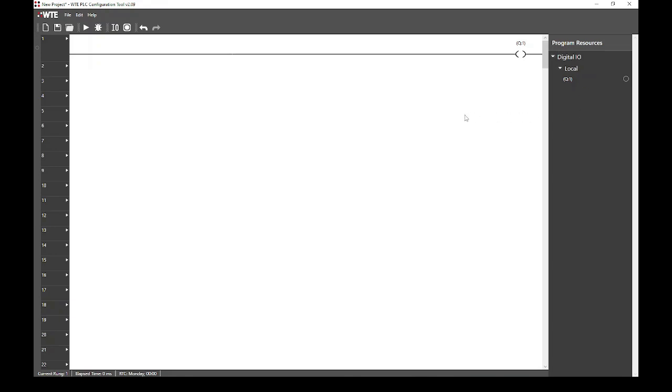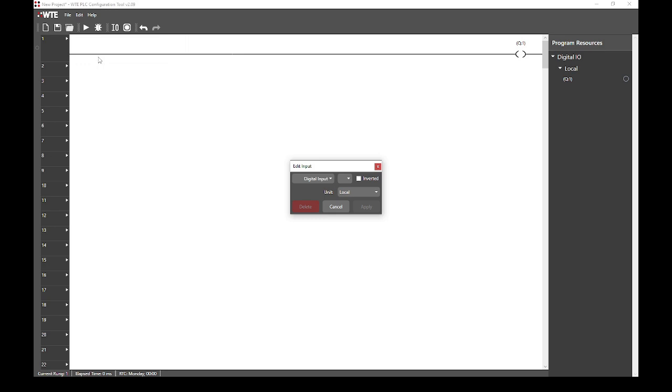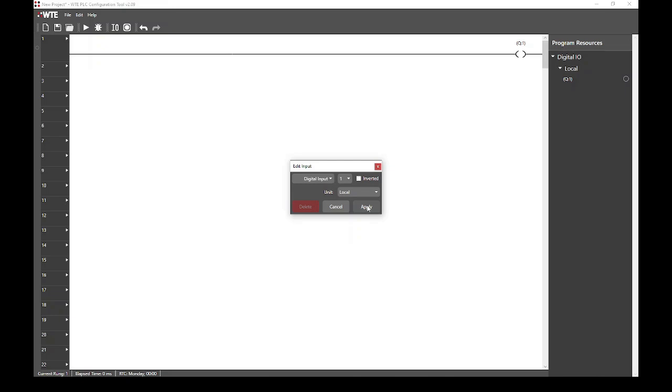The first step for this project is to hook in our motion detector on input 1. This is done by selecting the first rung input position. As you can see when we mouse over, this area of the rung is highlighted in blue. Clicking this area will allow us to configure the type of rung input. In this case, we want digital input 1. We then click apply to close the dialog.